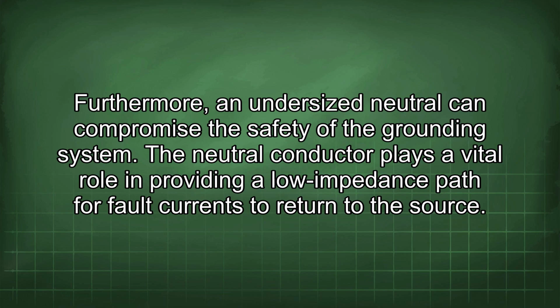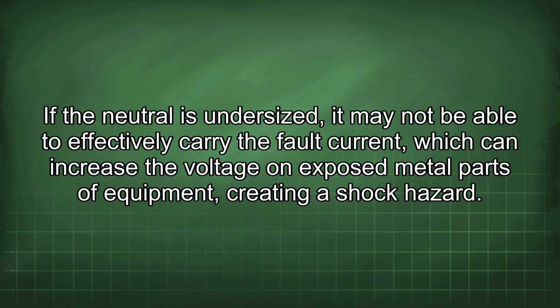Furthermore, an undersized neutral can compromise the safety of the grounding system. The neutral conductor plays a vital role in providing a low impedance path for fault currents to return to the source. If the neutral is undersized, it may not be able to effectively carry the fault current, which can increase the voltage on exposed metal parts of equipment, creating a shock hazard.